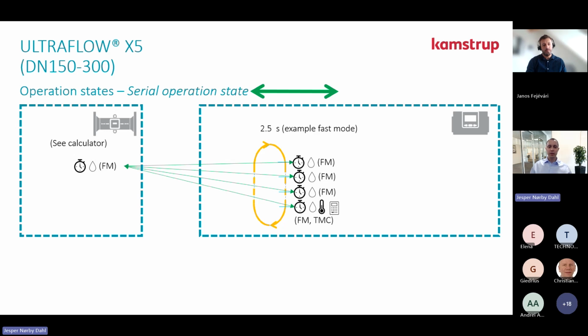And here, instead of having pulses, which is very volume related, it's time based. So it's the time between every one of these that matters. Why is this important? Well, if you want to use the flow or the volume for some kind of regulation, it could be pumps or valves you want to regulate according to the actual flow, then you cannot wait for a pulse signal if the flow is low. Here, because it's time-based, you don't have to wait anymore. You will have the actual flow almost immediately.